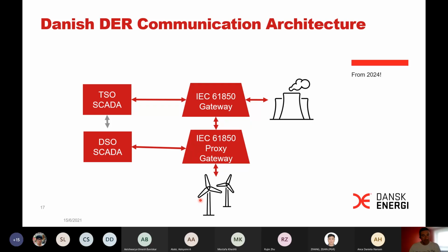The same requirements will propagate down to smaller units, all the way down to 1.5 megawatts. In the future, all units of 1.5 megawatts and larger will be expected to communicate in essentially the same way, but they will not communicate directly with the transmission operator. They will communicate with their local distribution company, and the distribution company will propagate that data through a so-called proxy gateway, which mirrors the data from many distributed units up to a single interface that the transmission operator can use, and also the distribution companies themselves will use the same server for importing this data for observability of their network.